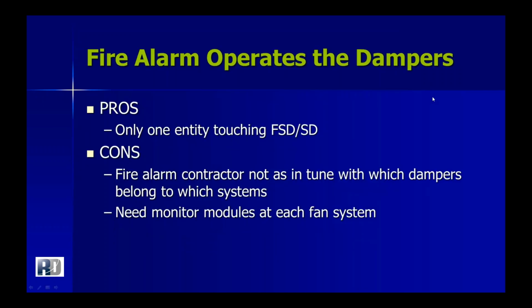Next, we'll look at fire alarm operates the dampers. So a pro here is only one entity touching the fire smoke dampers. So you don't have controls doing one thing and fire alarm doing another. The cons: the fire alarm contractor doesn't necessarily tend to be quite as in sync with the sequences or the functionalities of the dampers at all times, or even which dampers belong to which systems. And you also tend to require monitor modules at each fan system.